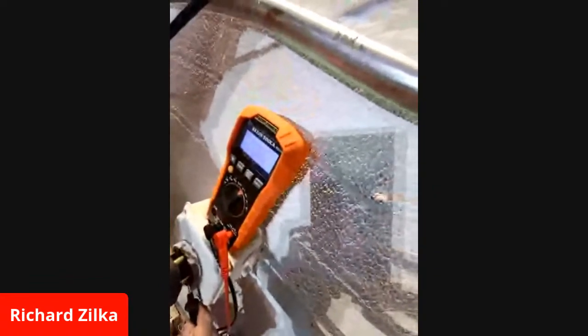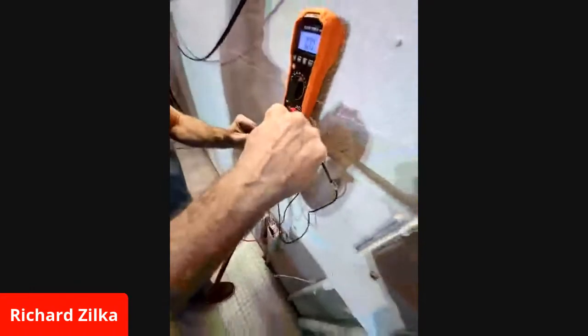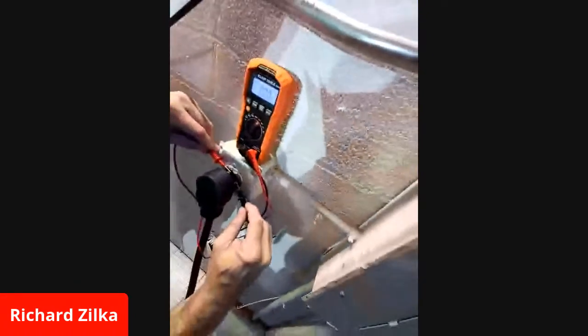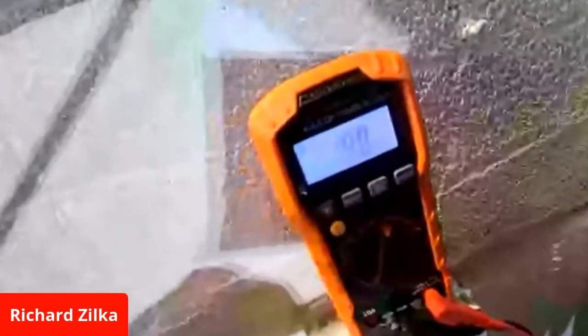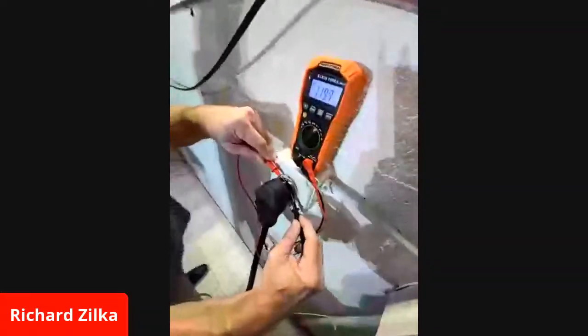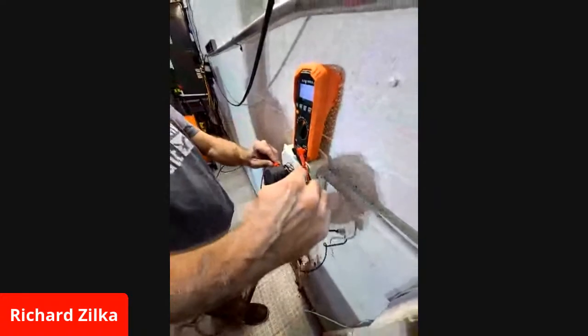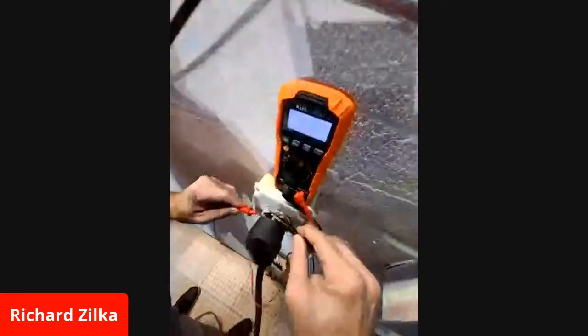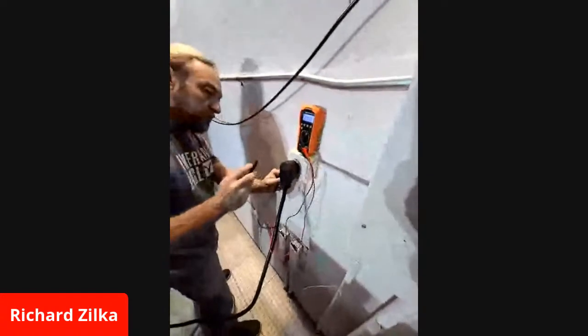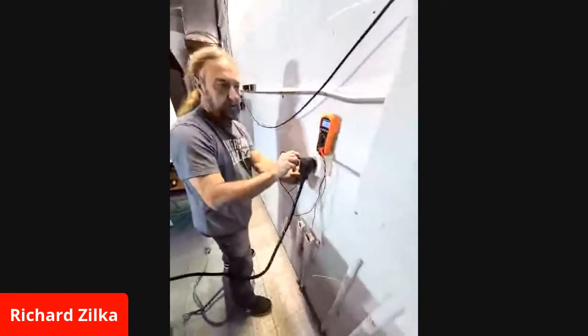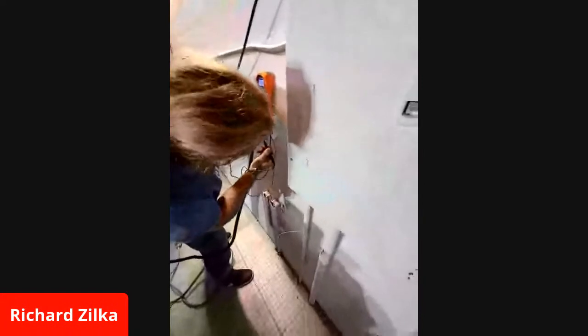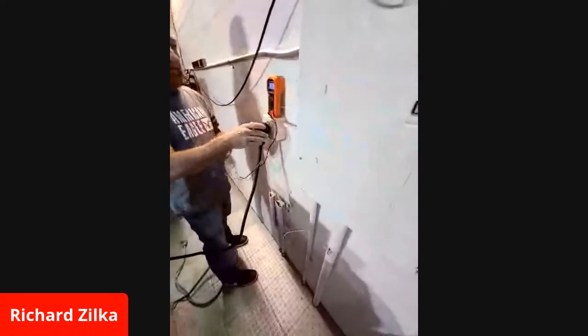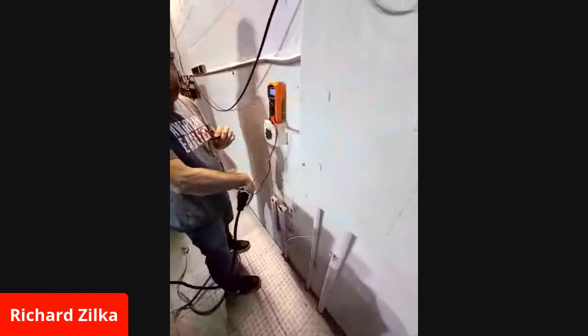Line 2 to neutral, I have 208. I'm going to check the ground. I have 120. You're slow, bro. Respectfully. Oh, okay. And I got 120. So line 1 and line 2 to ground gives me proper voltage polarity. But when I check neutral and one of the lines, I don't have proper power in the outlet. Oh, man. So we don't have proper power in our outlet. So let's go ahead and troubleshoot that.